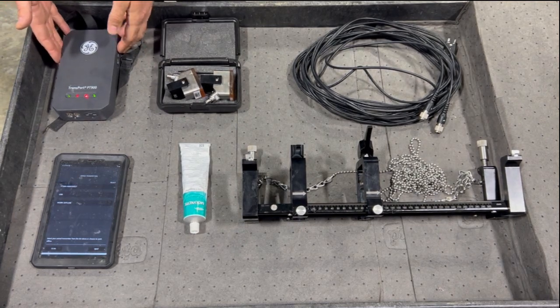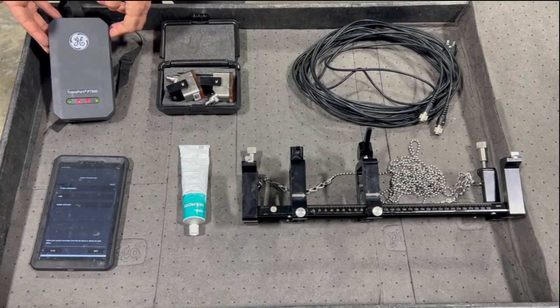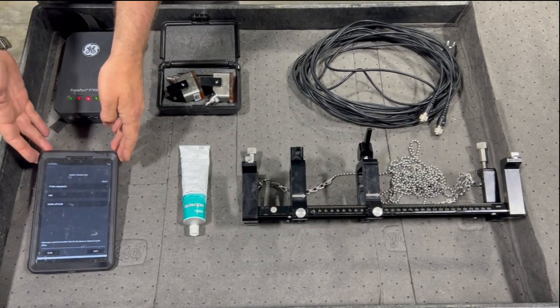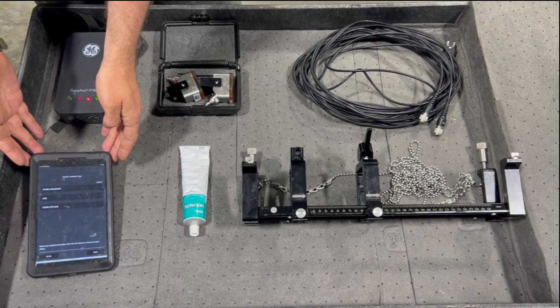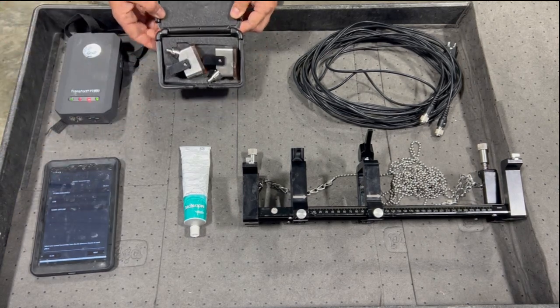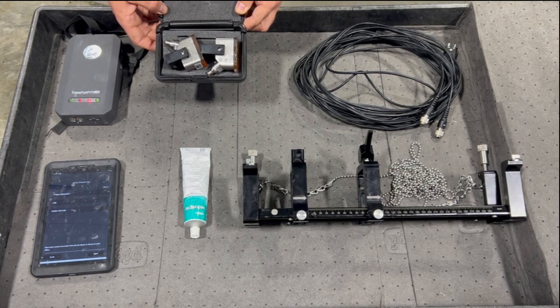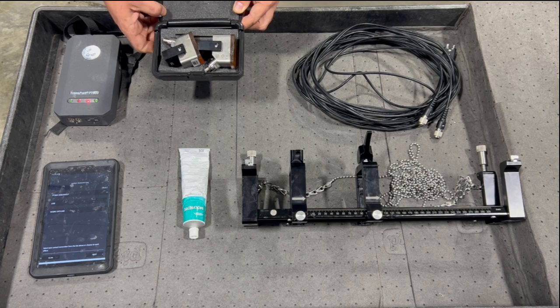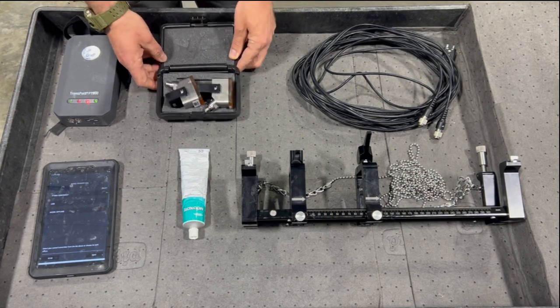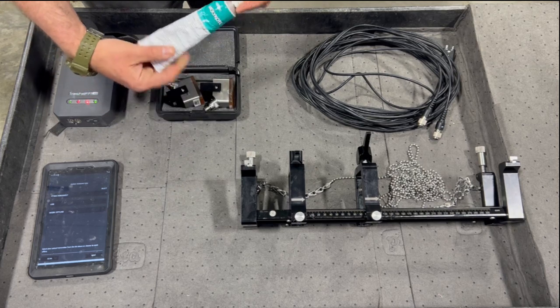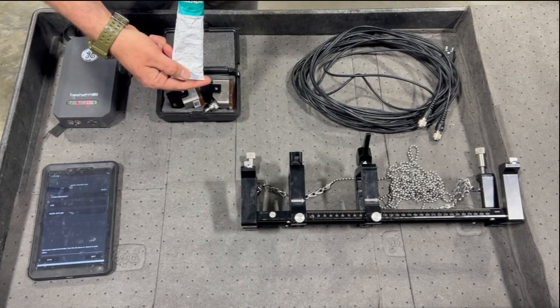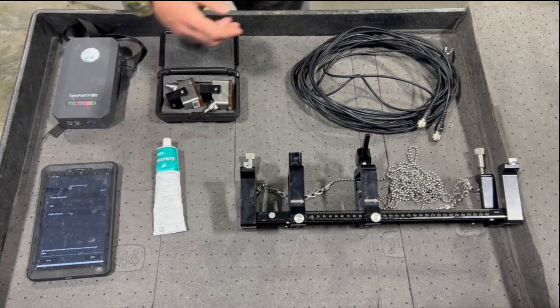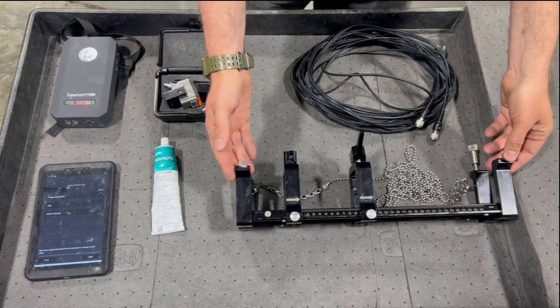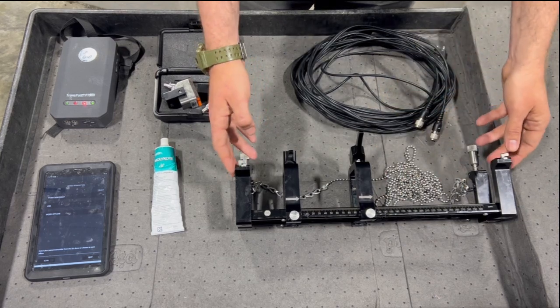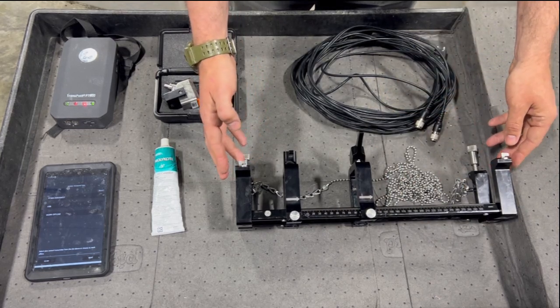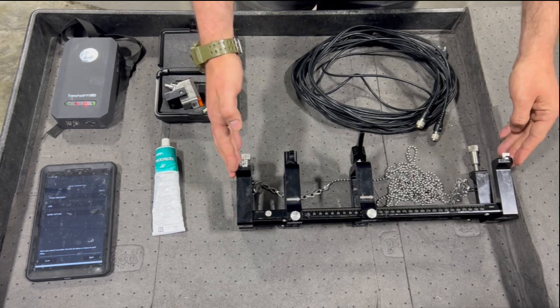So here we have the Transport PT900. This is the brain of the flow meter. We have an output screen so that we can see the flow rate and make adjustments real time. We have ultrasonic transducers that attach to the pipe and send a signal through the pipe and the water and give us real-time data on the flow rate. We have a compound used to apply on the transducers to get a better signal strength, a communication cable, and some kind of bracket with measurements along the side so that we can hold the transducers in place at the specified distance to get the most accurate flow rate possible.